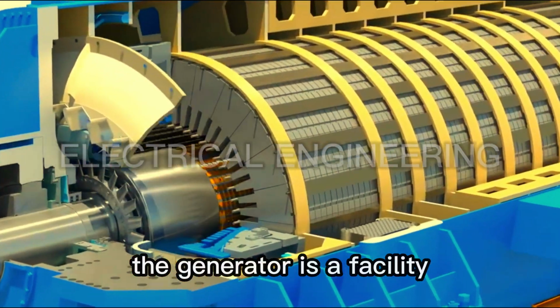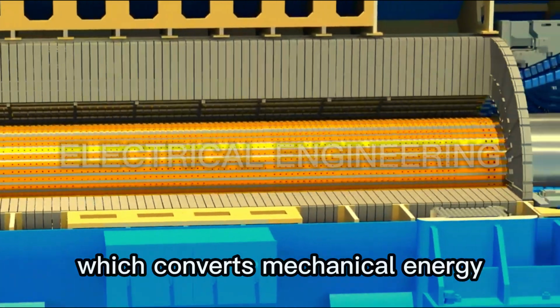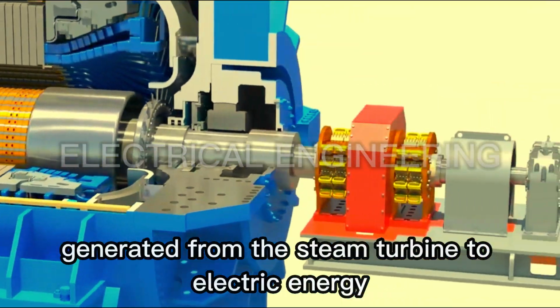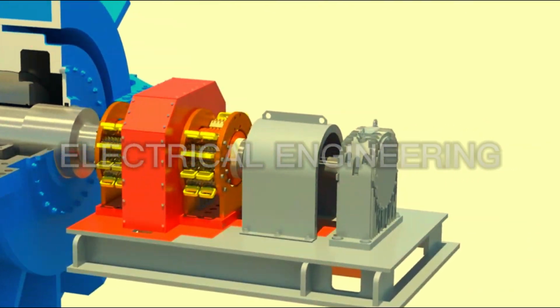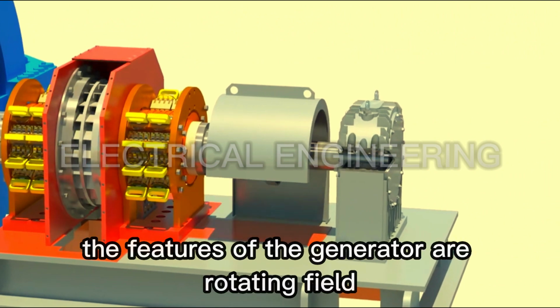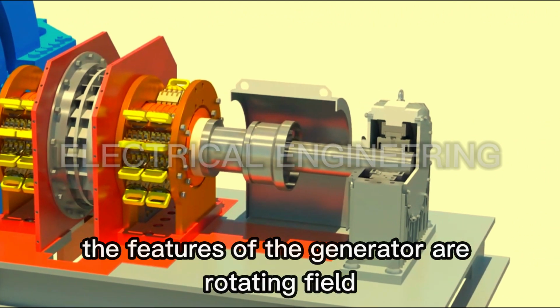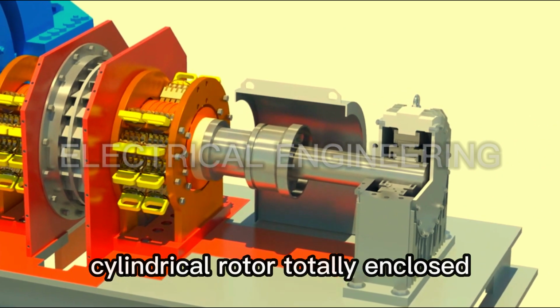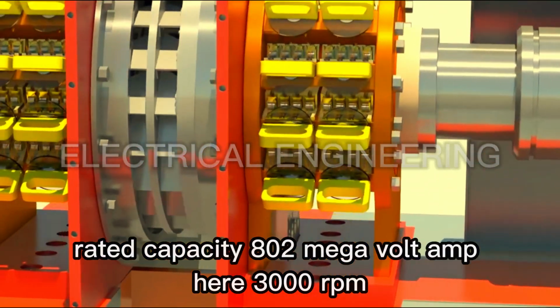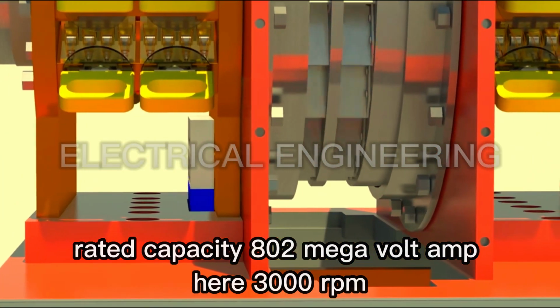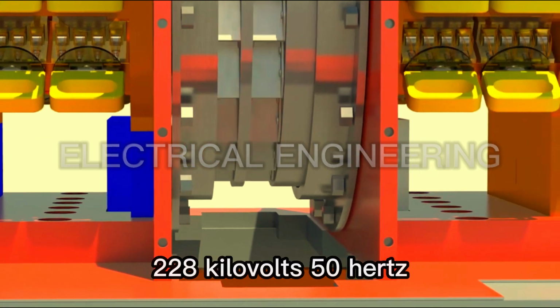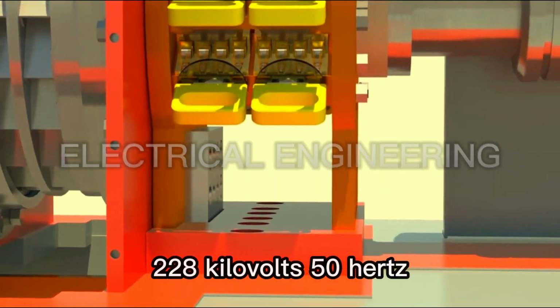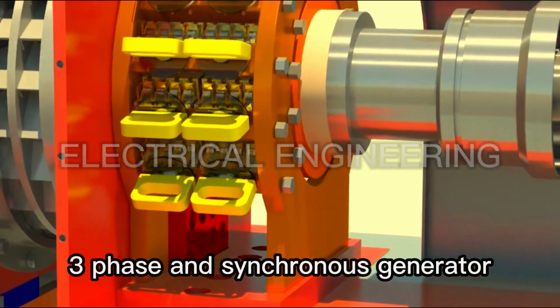The generator is a facility which converts mechanical energy generated from the steam turbine to electric energy. The features of the generator are rotating field, cylindrical rotor, totally enclosed, rated capacity 800 megavolt ampere, 3000 revolutions per minute, 22.8 kilovolts, 50 hertz, 3-phase and synchronous generator.